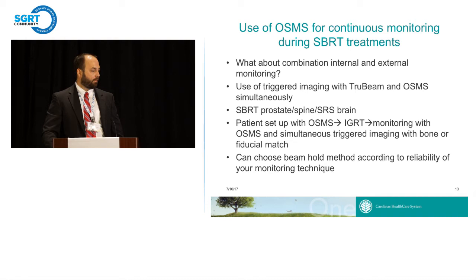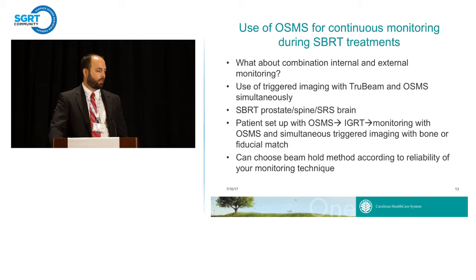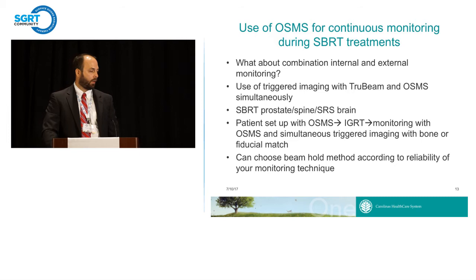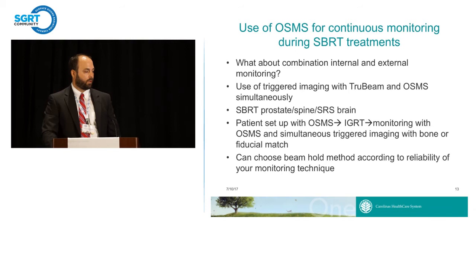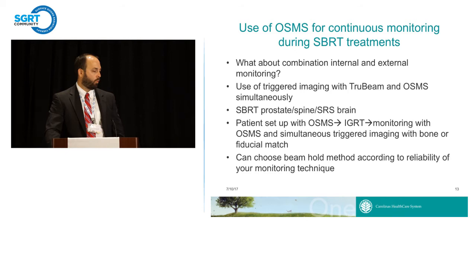There are various techniques for continuous KV imaging on different machines. On our TrueBeam we've been exploring combining internal and external monitoring using triggered imaging capabilities simultaneously with OSMS. Within SBRT it's very logical to use this combination, and we've been using it for prostate, spine, and SRS brain patients. The process is to set up with OSMS, do IGRT, then monitor with OSMS while simultaneously doing triggered imaging with either bone or fiducial match during treatment. One current limitation is that you have to choose your beam hold method — you can't hold the beam with both OSMS and triggered imaging — so we pick whichever monitoring technique we feel is more reliable.